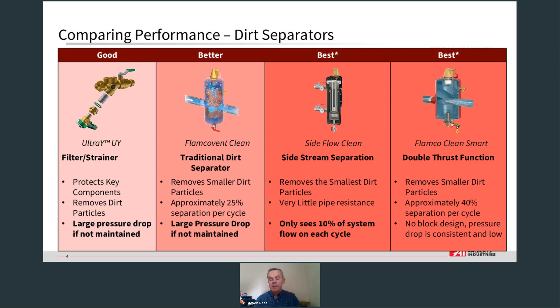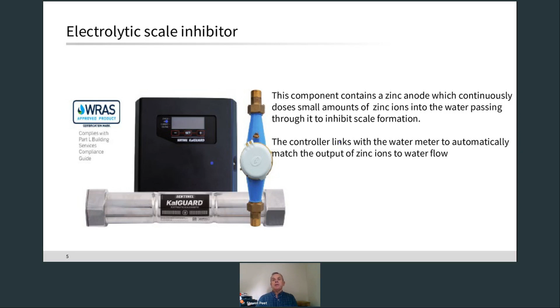So that's air and dirt. Next, we have scale removal. Accumulation of scale also reduces the efficiency and lifespan of the system. Part L suggests a chemical water treatment formulation should be added to the primary circuit to control corrosion and the formation of scale and sludge. At Flamco, we use a natural electrolytic process to prevent limescale encrustation. The unit imparts a tiny amount of soluble zinc, which interferes with the crystal structure of scale-forming water hardness minerals so they can't form hard, stubborn scale on pipework. It's a really low maintenance way to protect the system against the damaging and expensive impact of limescale.